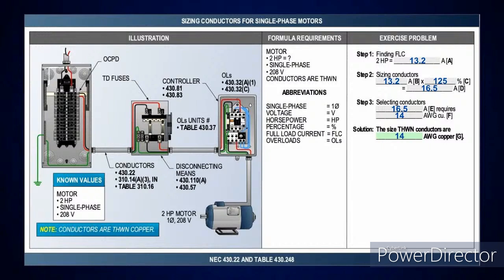If you pick up your 208 volt, come across, pick up 2 horsepower, that's going to give you 13.2 amps. And then 430.22 states that if you have a single motor, you need to take it at 125%. So I'll take the 13.2 amps times 125%, which gives me 16.5 amps. Then just go over and look at table 310.16. It'll tell you the next size above that is a 14 copper conductor.